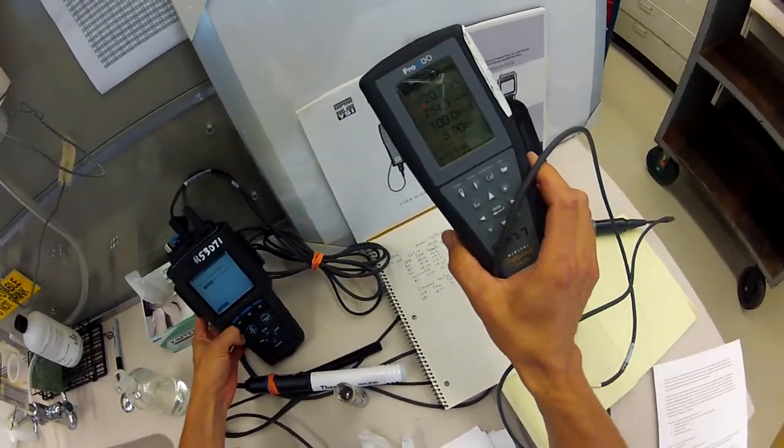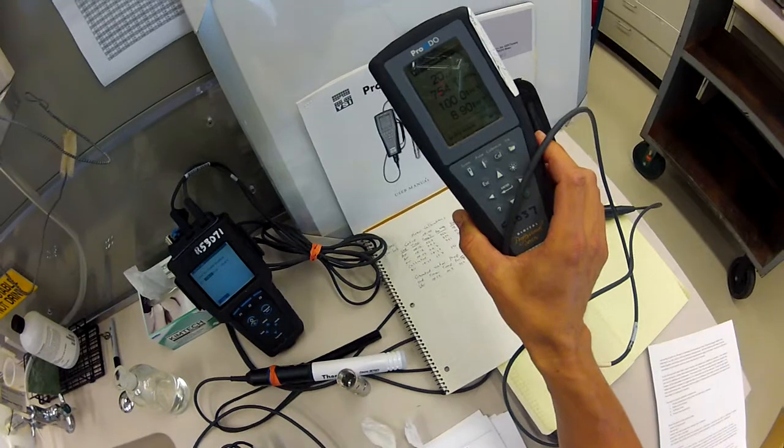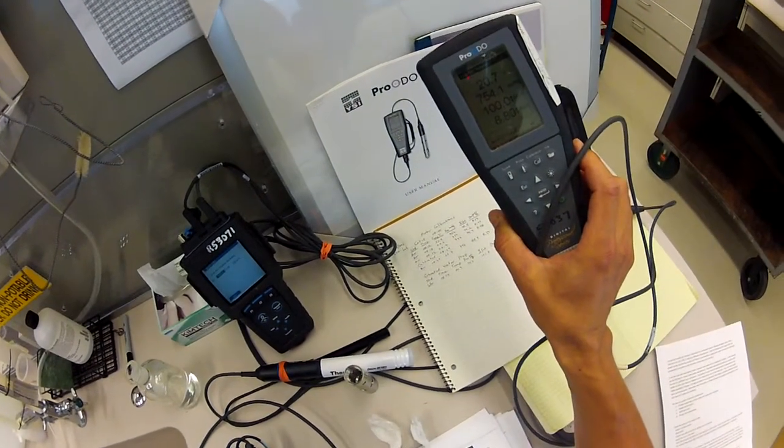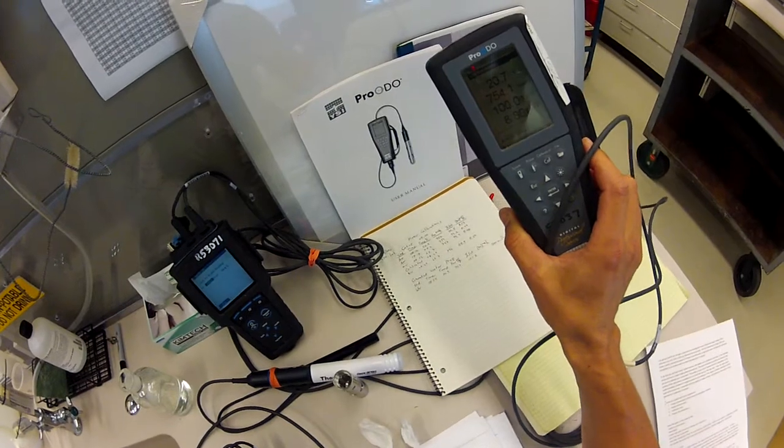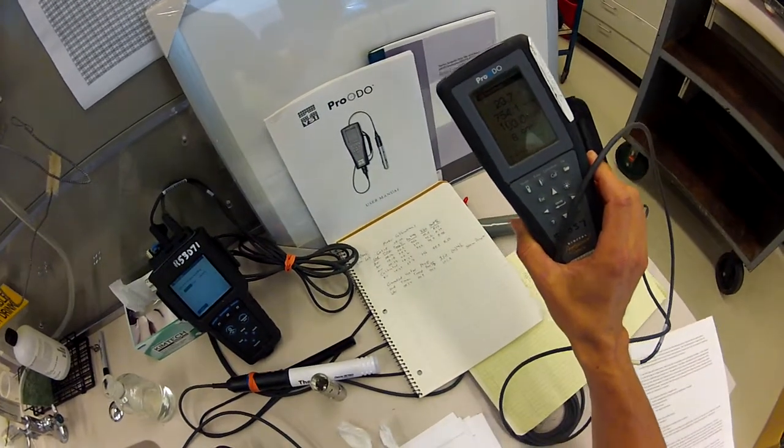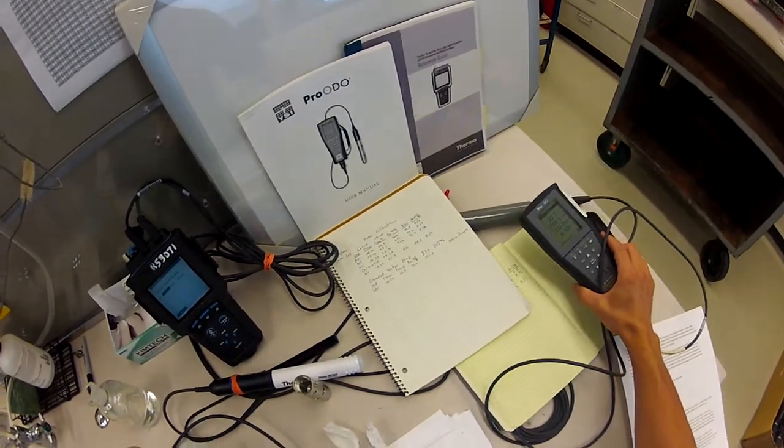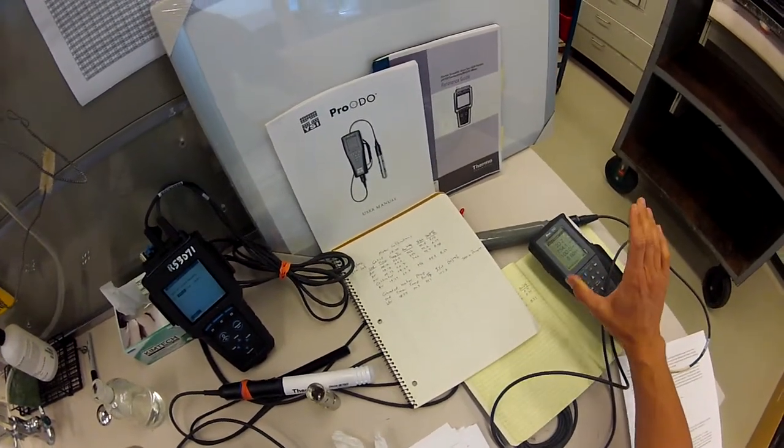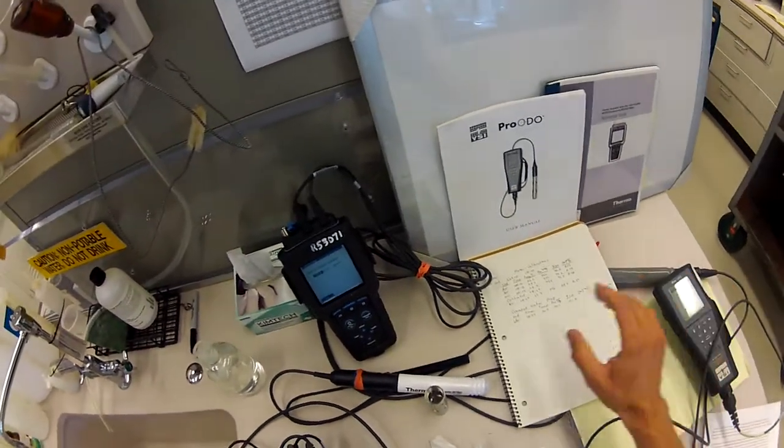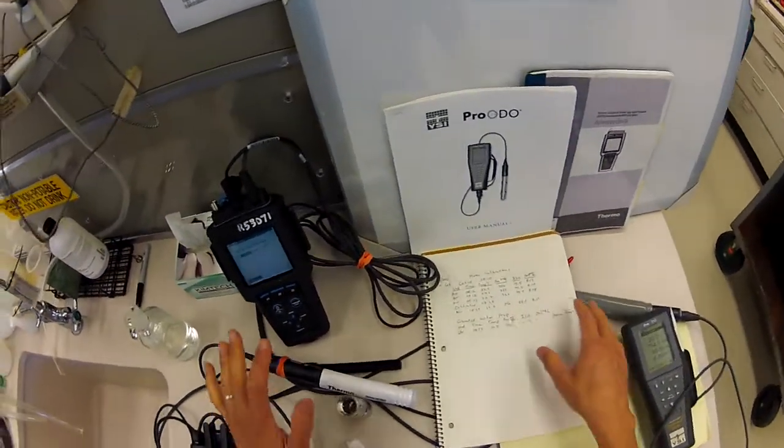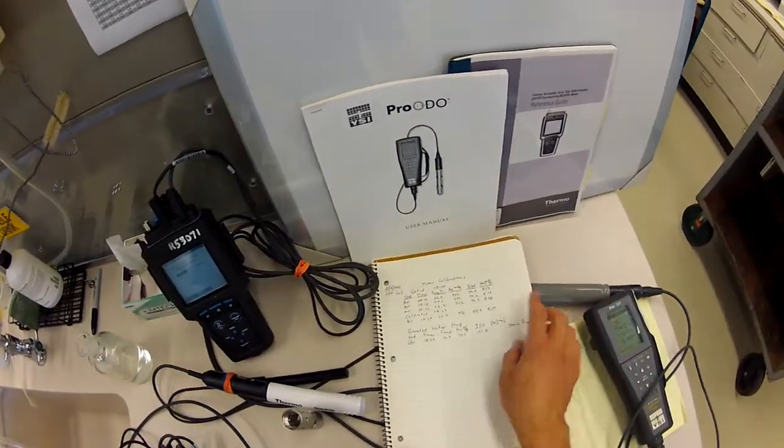If you're using the YSI, you want to make sure when you're doing your calibration that you are working in percent local - that's referring to the barometric pressure. Sometimes, particularly YSI meters in our experience, will give you a corrected barometric pressure at the sea level, and you want the local barometric pressure.